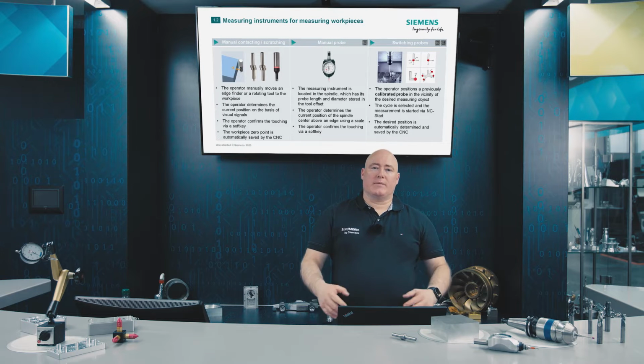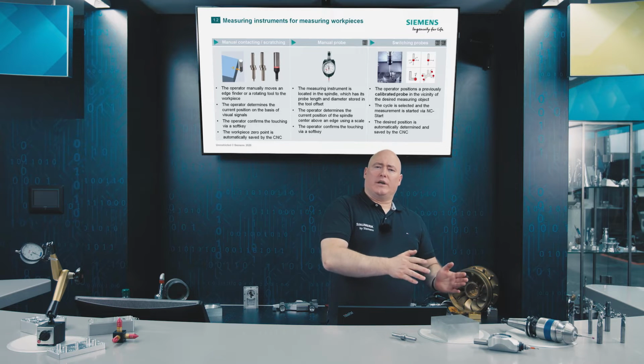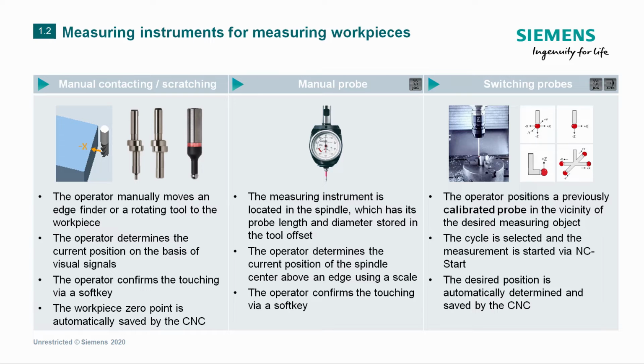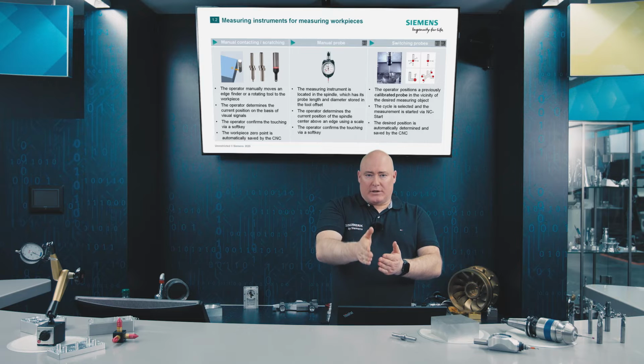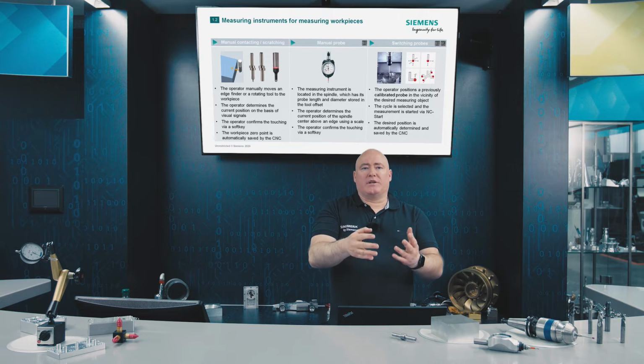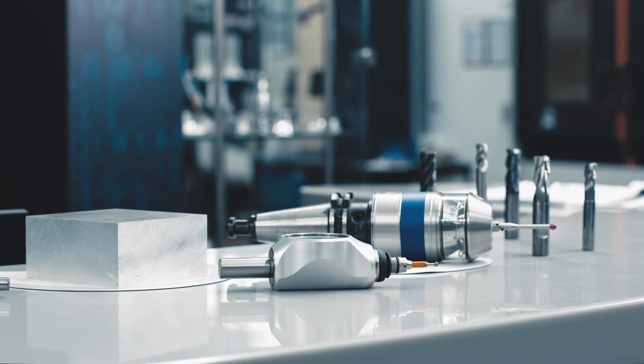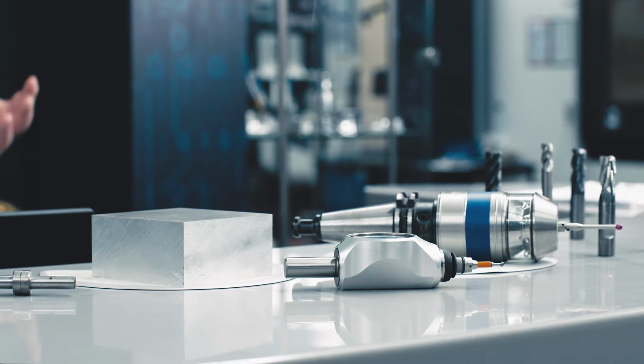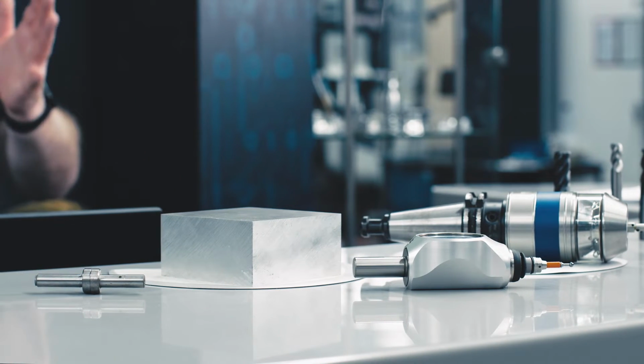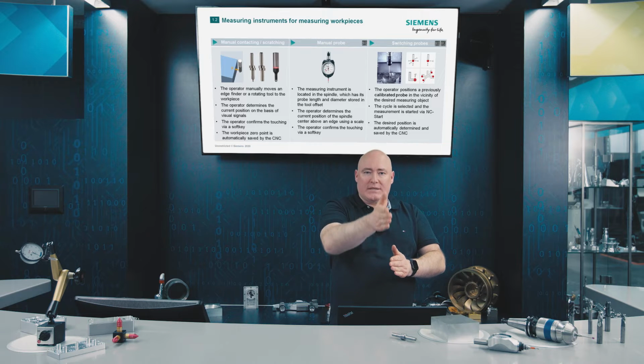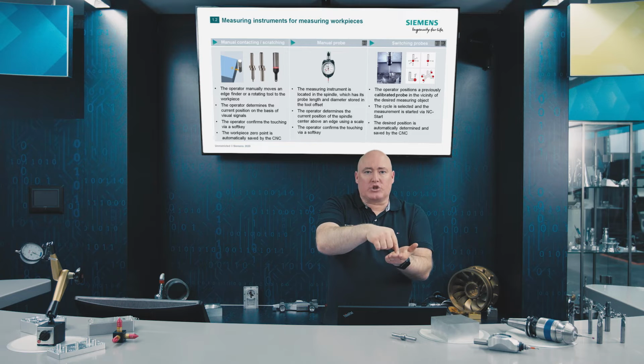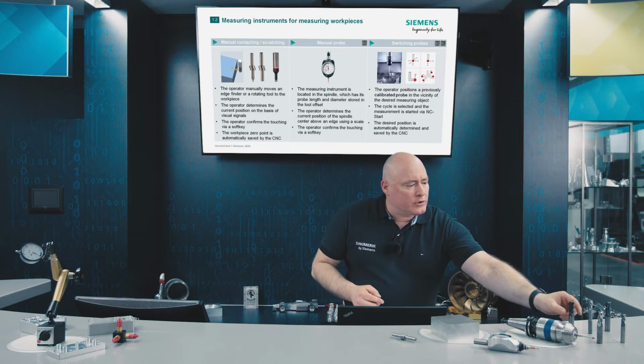There are different measuring tools available for measuring workpieces. These range from traditional, in other words conventional test or measuring methods, to analog probes and touch trigger digital 3D probes. But whatever the method we choose, the aim is always to move or position the milling spindle precisely over a defined workpiece edge that we've determined ourselves. We want to communicate the position and alignment of the workpiece in the machine coordinate system to the control system so that the machine knows where my workpiece is. For the purpose of orientation, we determine an edge, and the center of the milling spindle is precisely what has to be positioned above the edge. We can use various methods for this procedure.